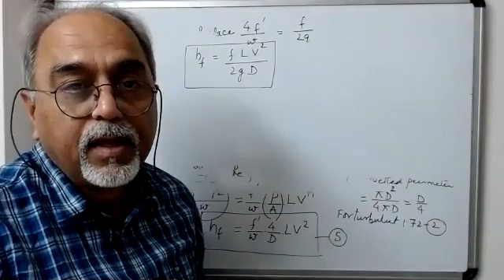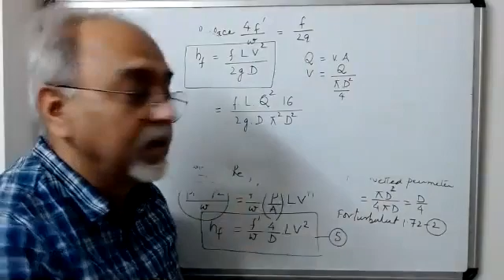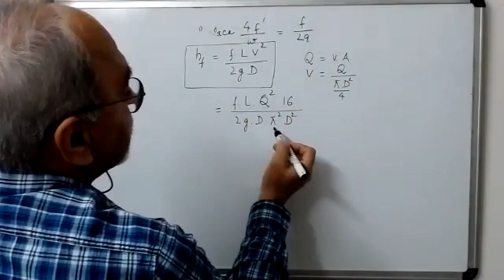FLV square by 2GD. Now in this case, if I want to write this expression in terms of discharge instead of velocity, if I replace it by discharge, what is discharge? Q is equal to V into area, or V is equal to Q upon area, that is Q upon pi d square by 4. Since it is squared, so this will be F L Q square into, of course, 4 square, that is 16, by 2 G D and pi square d square. Kindly check this replacement of the symbols, these expressions. There are some constants around, 16, 2g, pi square, etc. So this comes out to be F L Q square upon 12.1 times d to the power 5.